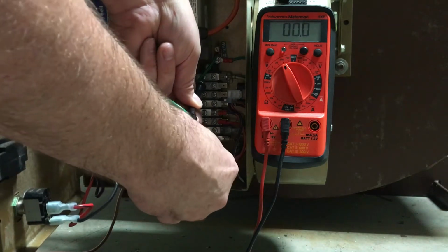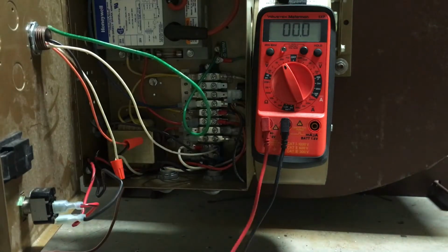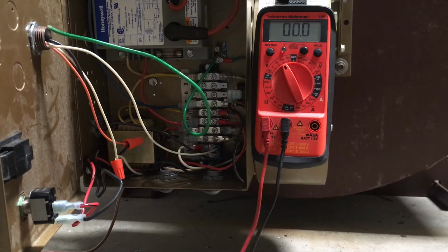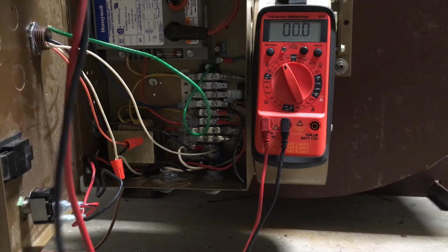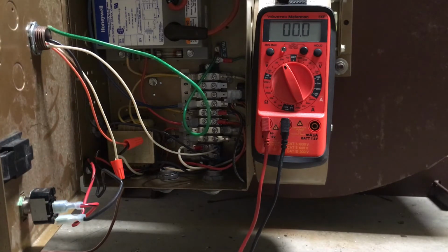So you want 5 and 10 where we do not have anything. So it appears that maybe that switch has failed of some sort. The first thing to verify, again, everything is always supposed to be done when the system is supposed to be operating, supposed to be burning.